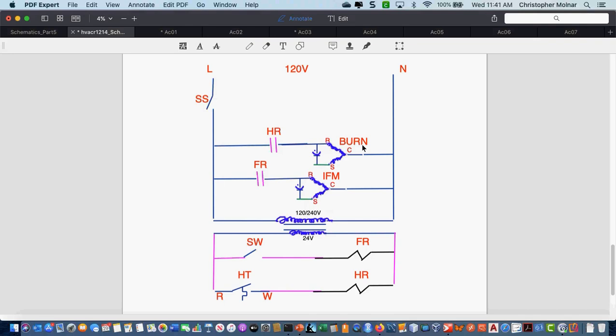Switch SW closes, powers my fan relay, closes the normally open FR, and powers my indoor fan motor. System runs until the thermostat satisfies and opens. Then something eventually is going to open my SW and turn my fan motor off. This is the basic oil burner system. We have more components we need to add, but this is basically what's happening in an oil forced air furnace.